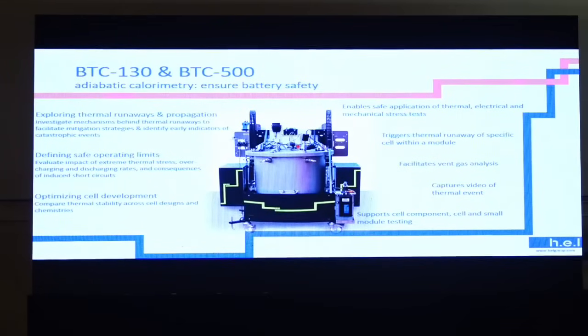So these are the two types of products or calorimeters that we make, in which you can perform electrical stress, thermal stress, as well as mechanical stress, that is nail penetration and crash testing. We also have provisions for testing the gases which come out, and those could be toxic. In the third case, where there is an extreme fire, that will also lead to a lot of toxic gases being produced. And if we want to analyze whether those toxic gases are harmless, we have provisions for doing that also in this particular device.